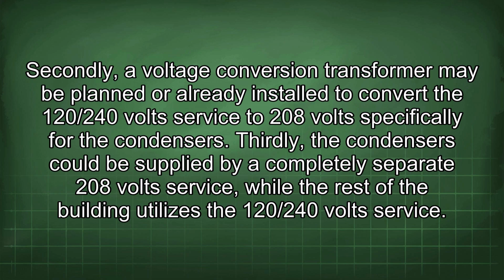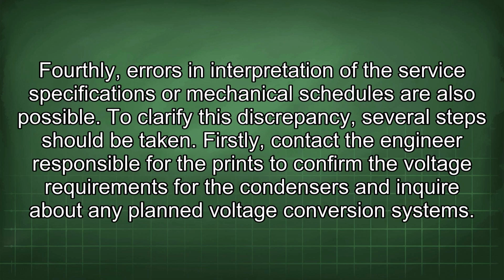Thirdly, the condensers could be supplied by a completely separate 208 volt service, while the rest of the building utilizes the 120/240 volt service. Fourthly, errors in interpretation of the service specifications or mechanical schedules are also possible. To clarify this discrepancy, several steps should be taken.